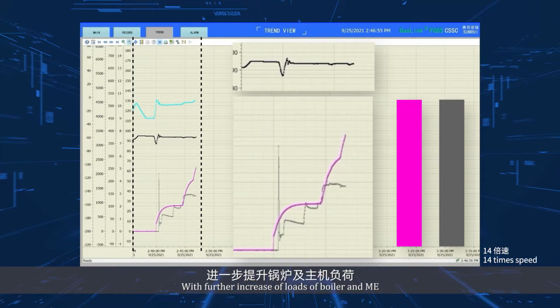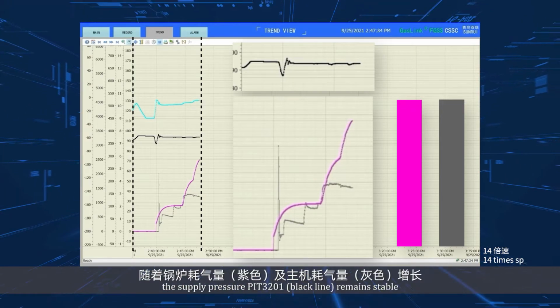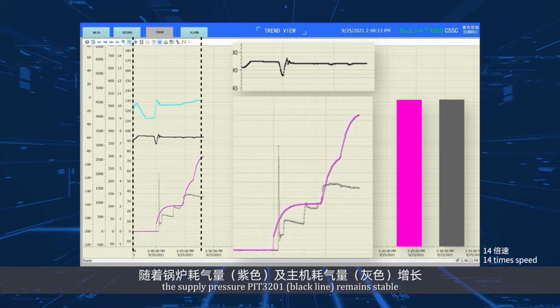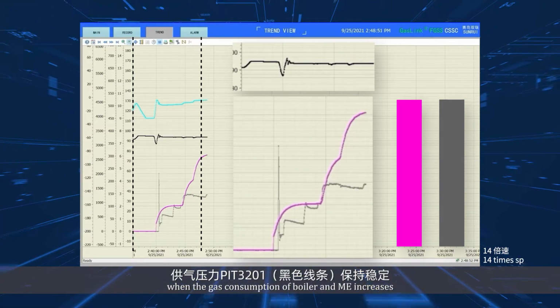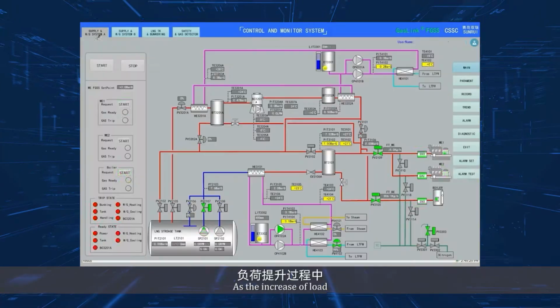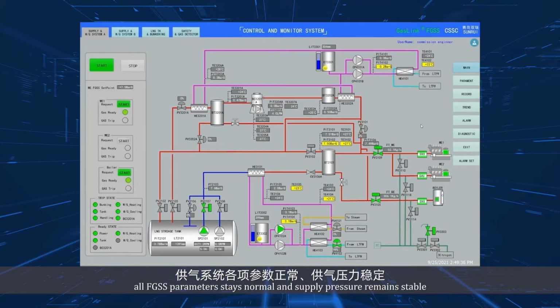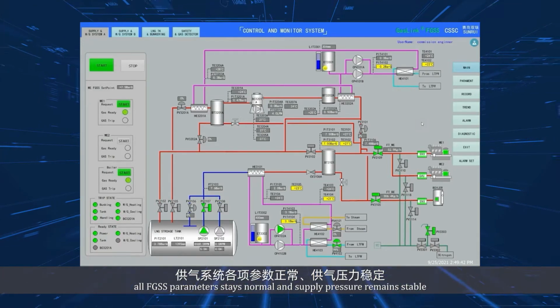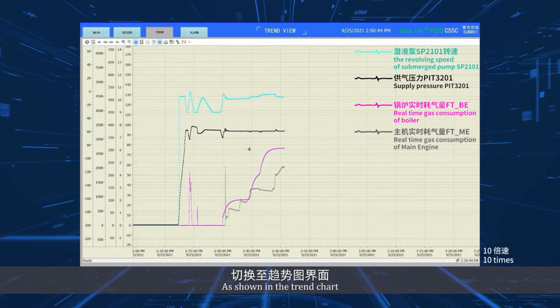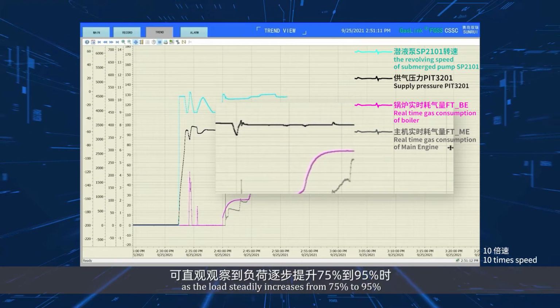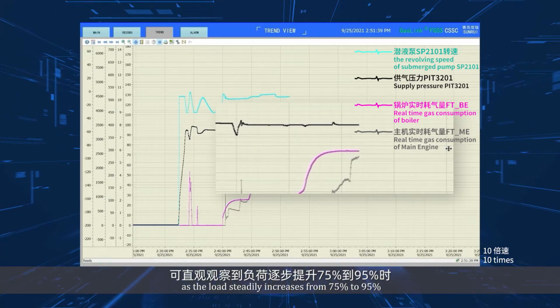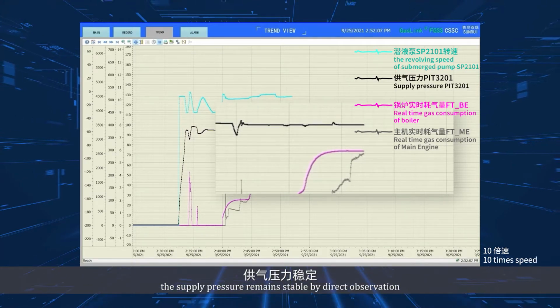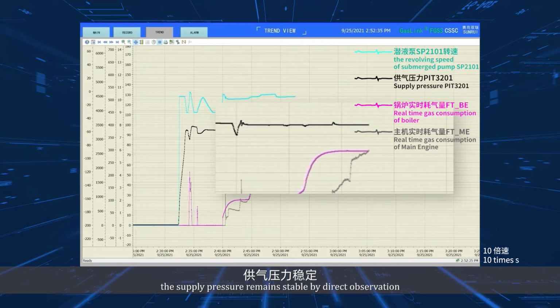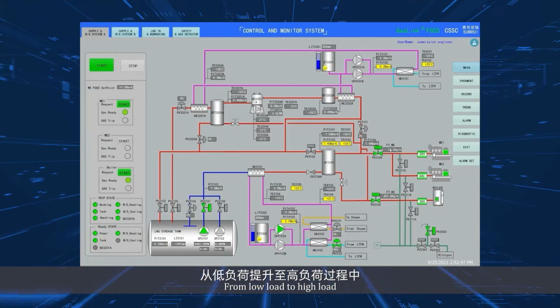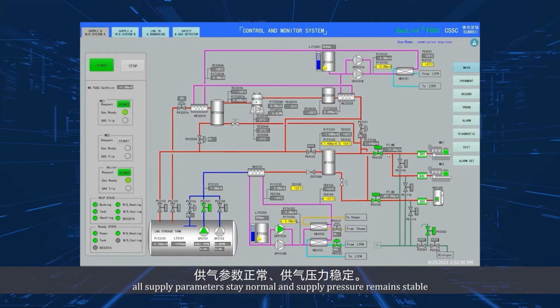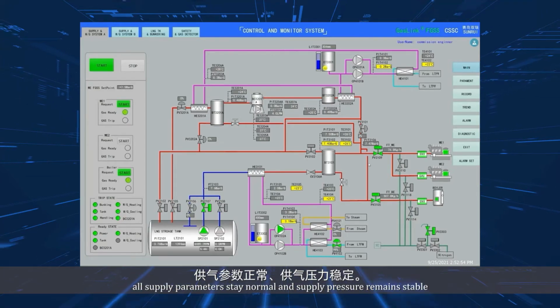With further increase of loads of boiler and ME, the supply pressure PIT3201 black line remains stable when the gas consumption of boiler and ME increases. As the load increases, all FGSS parameters stay normal and supply pressure remains stable. As shown in the trend chart, as the load steadily increases from 75% to 95%, the supply pressure remains stable by direct observation. From low load to high load, all supply parameters stay normal and supply pressure remains stable.